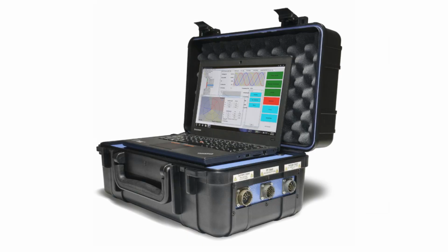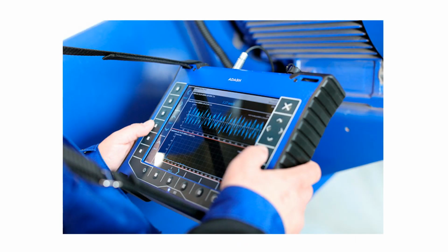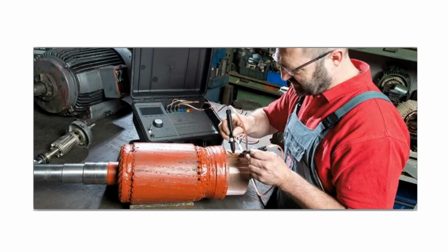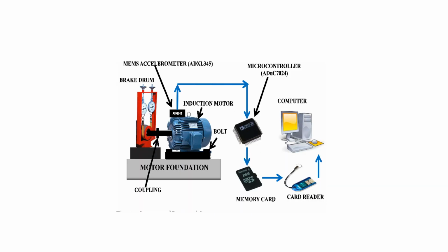Once we know how faults reveal themselves, whether in current harmonics, increased losses, unusual torque ripples, or rising temperatures, we can design smarter diagnostic systems. Simulation provides the fingerprints of each fault, so real-world monitoring equipment can recognize them at the earliest stage.